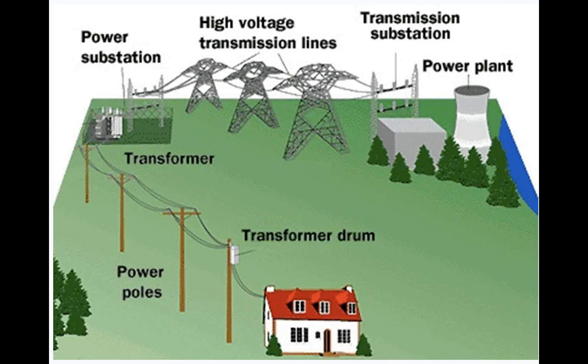We step it down with a transformer, and this could be a pole top or a pad mount transformer. We step down the primary voltage to what we call secondary voltage. Secondary voltage is always the same voltage. It's usually a 120 and a 120, two hot legs, and a bare neutral. And that's what goes to the customer. So that's where we are.